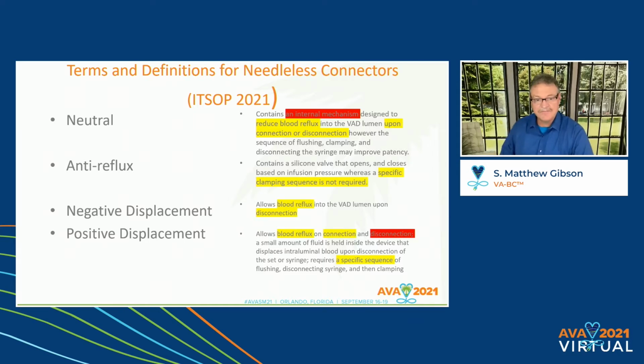The negative displacement allows blood reflux on disconnection - this is 100% true. Positive displacement, by definition, allows blood reflux on connection and disconnection. Here, the words in red are part of issues that I have found. The positive displacement goes on to say that the small amount of fluid is held inside and it pushes out, and it does require a specific clamping sequence - you flush, disconnect, and then clamp.